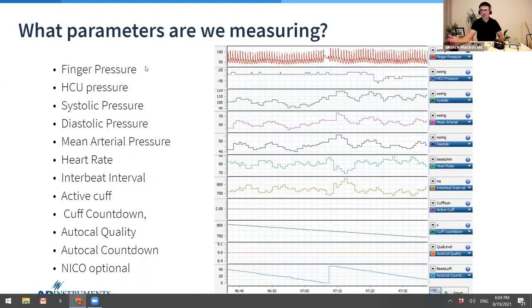Obviously, the first channel will be finger pressure. That's clearly, you can see that. The HCU pressure, that's the height correction unit pressure. That's the pressure we really should be looking at if a subject tends to be moving their hands around a lot. If they happen to be stationary like I am and not really moving around, then the finger pressure would be totally fine to use, provided that your hand is fairly at the same level as the heart level, so it should be a good representation.